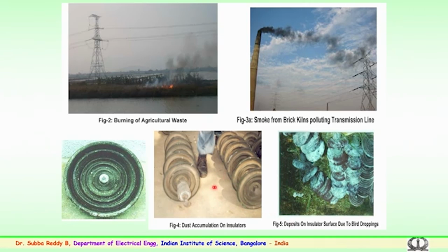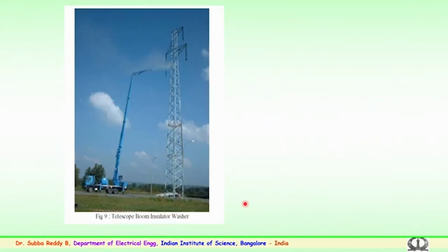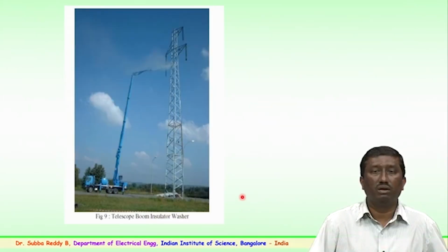So, this is one more example of how the dust, particularly near the cement factories or some quarries, goes and settles over a period of time and makes the insulator completely polluted, and it may lose the insulating properties for which it is designed. So, some remedial measures for the insulators. Much before the monsoon starts, remedial measures are taken by the electricity authorities or the utilities to see that the flashover does not happen.